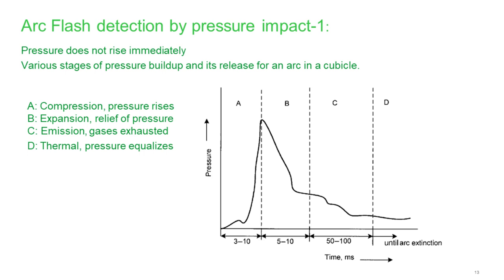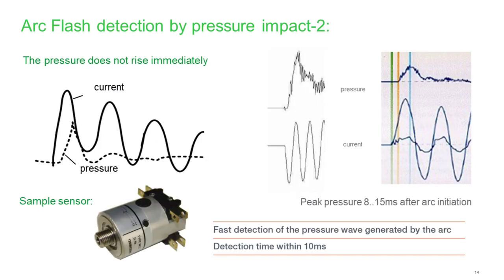The pressure increase in the cell takes some time. On the right-hand side, when we increase the current, the maximum pressure peak comes almost 10 milliseconds after the current waveform. Even manufacturers of pressure sensors dedicated to arc flash detection acknowledge that detection time is around 10 milliseconds. This shows that pressure-based detection is inherently slower.